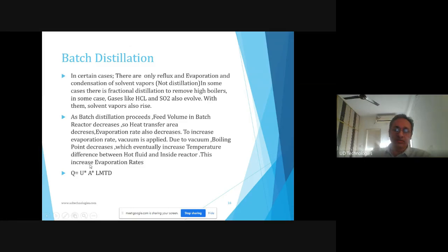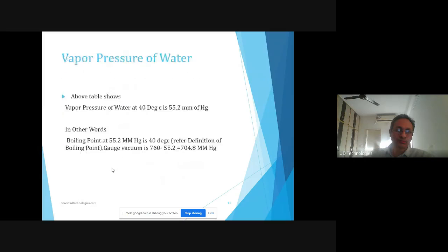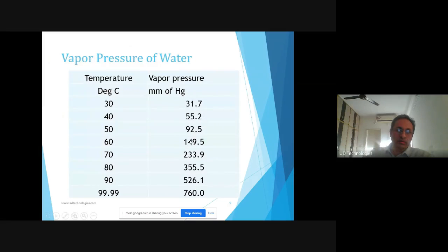So we can see from this equation, area is constant, U is constant. We are increasing LMTD. Let me take one example. Let's suppose we are boiling water in the reactor and we are applying 125 degree steam in the jacket. So what is the temperature difference? That is only 25 degrees. If we apply the vacuum to around 92.5 mm of Hg, the boiling point will be 50 degrees centigrade. So the temperature difference will be 125 minus 50, that is around 75. Earlier it was only 25 degrees.